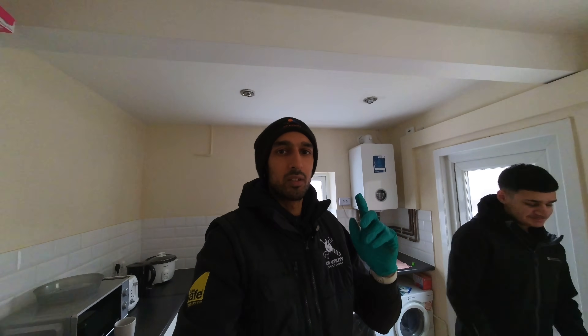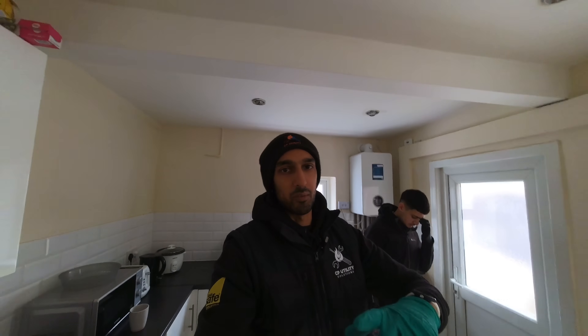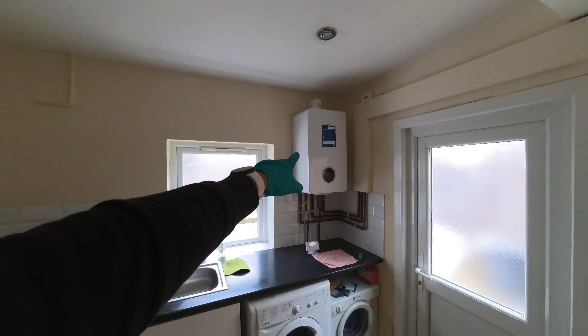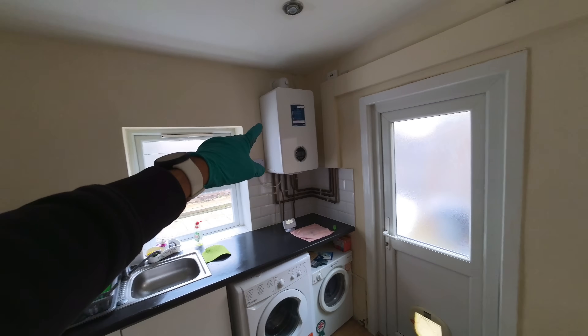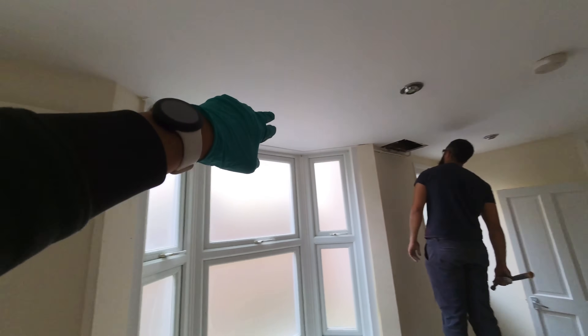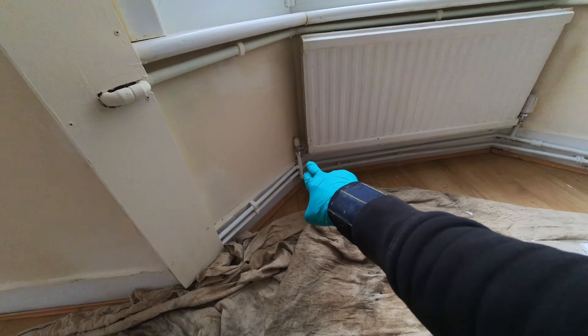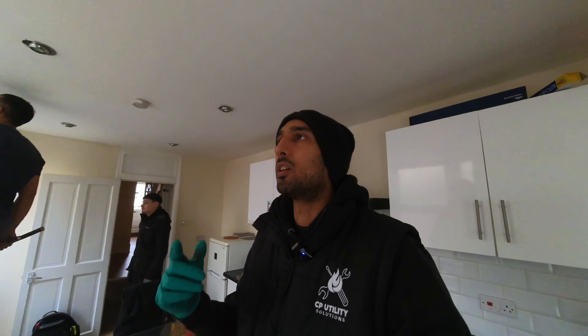Welcome back to this job - you might remember it from back in December. The job was a combi boiler conversion; the old heat-only boiler was replaced and they moved the new boiler across. We need to get the primary pipework from up in the ceiling space and bring it along the window frame to connect properly, because currently the heating pipework has just been teed onto the radiator pipework. We've got some circulation issues - only two radiators aren't working, but it still needs to be resolved.